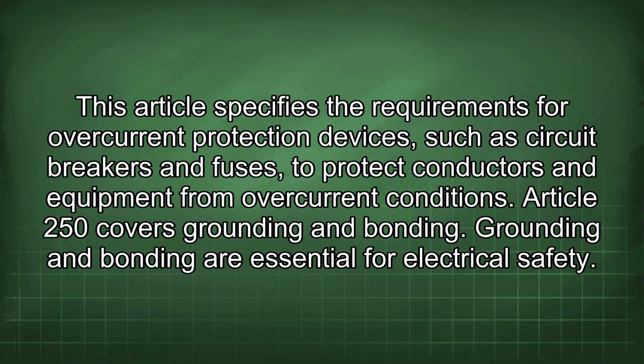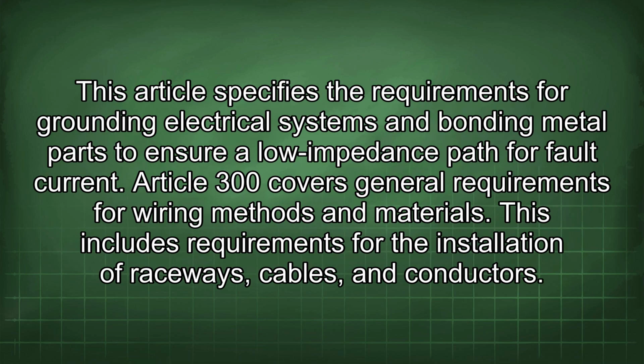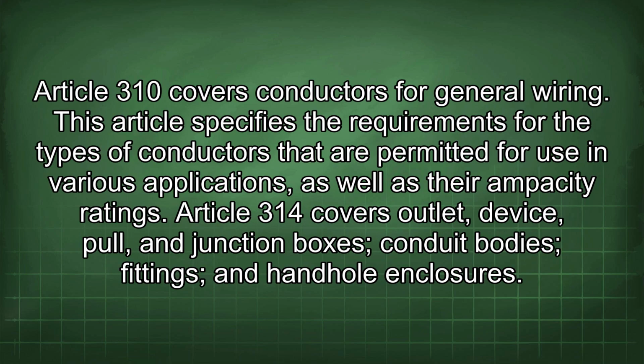Grounding and bonding are essential for electrical safety. This article specifies the requirements for grounding electrical systems and bonding metal parts to ensure a low impedance path for fault current. Article 300 covers general requirements for wiring methods and materials. This includes requirements for the installation of raceways, cables, and conductors. Article 310 covers conductors for general wiring.